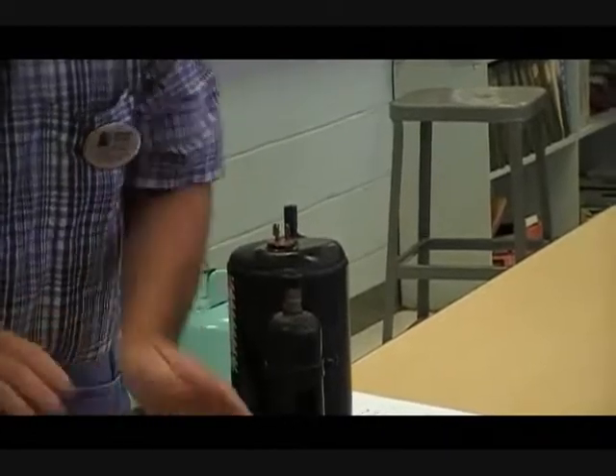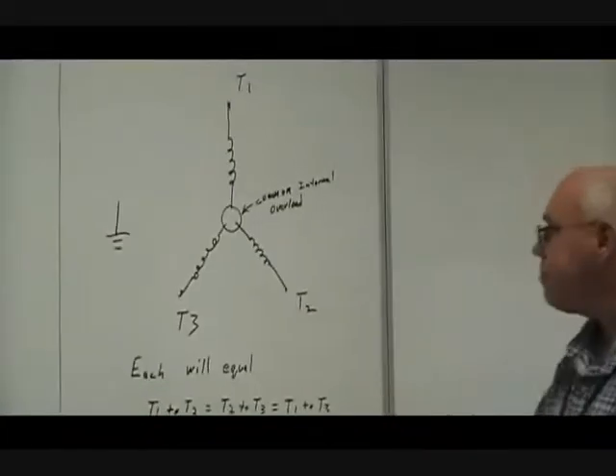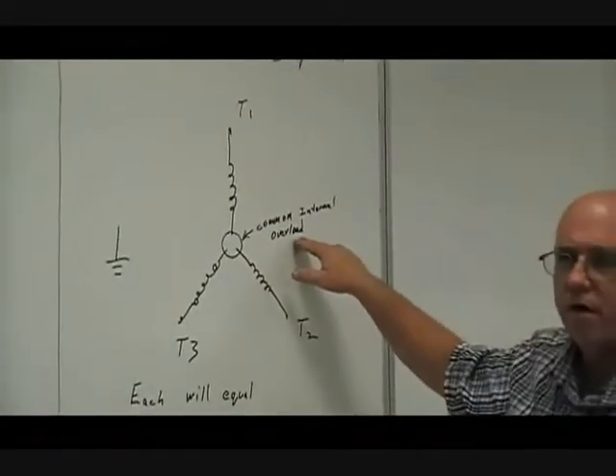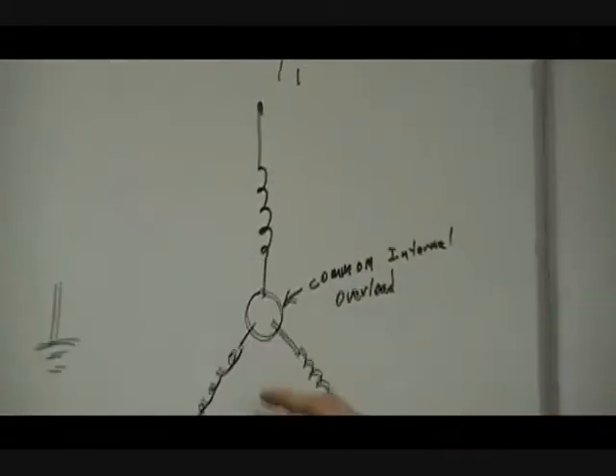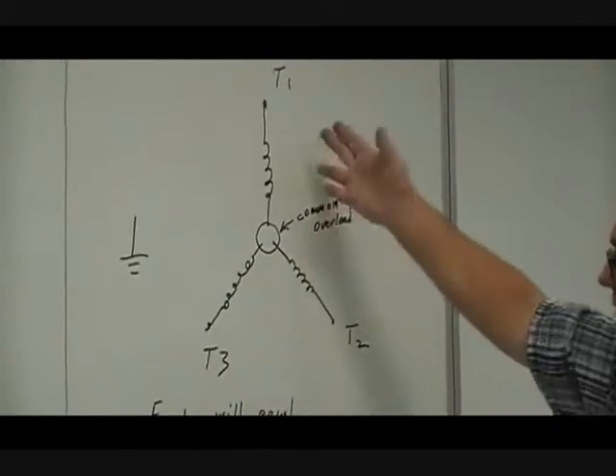Three phase, I want to swap over to three phase for just a moment. You see the three phase windings here. The three phase have a common internal overload on many compressors. Some do, some do not. But when you do, if it's open, you will not have continuity between any of the phases.